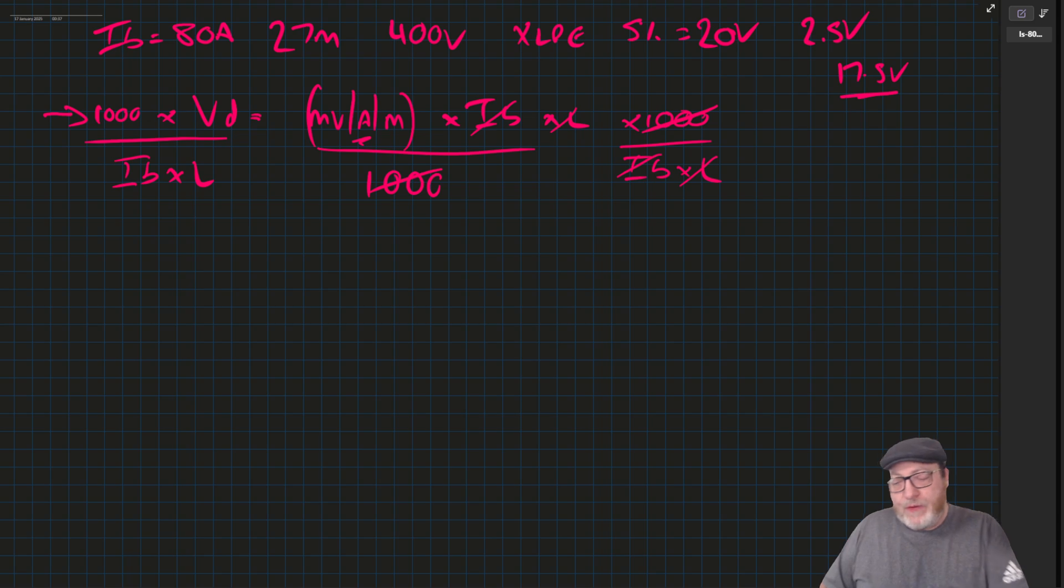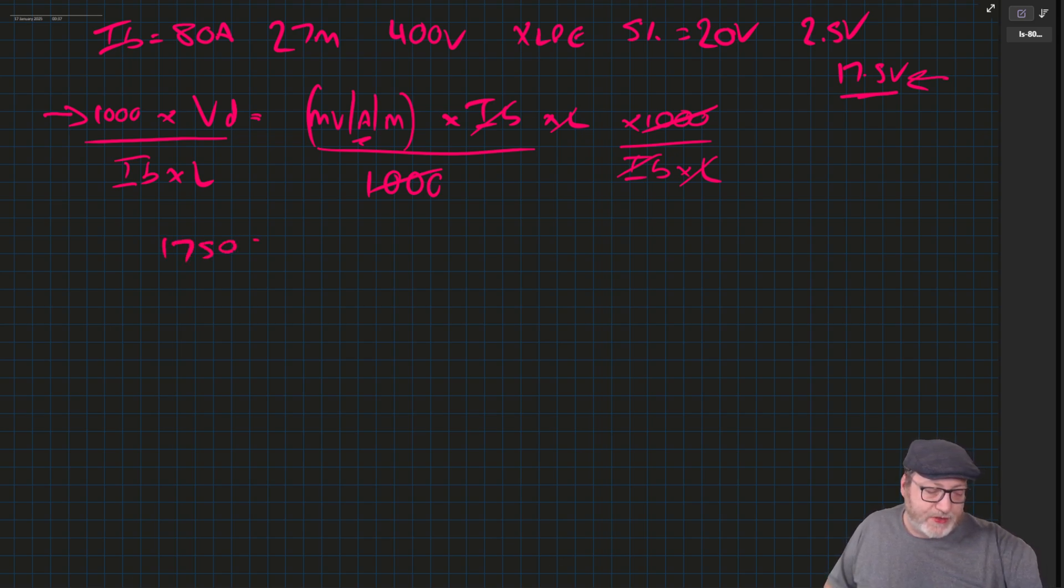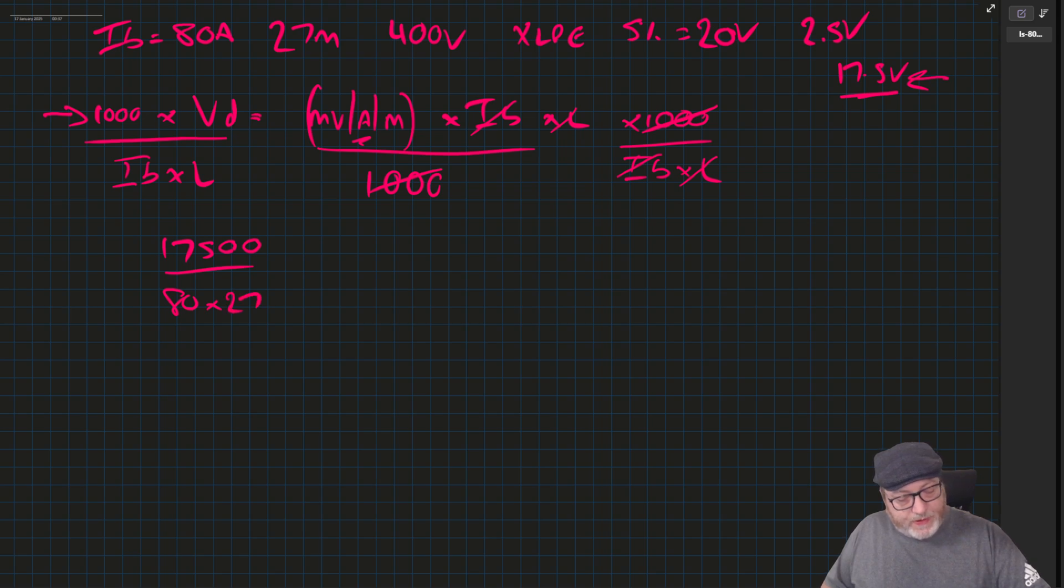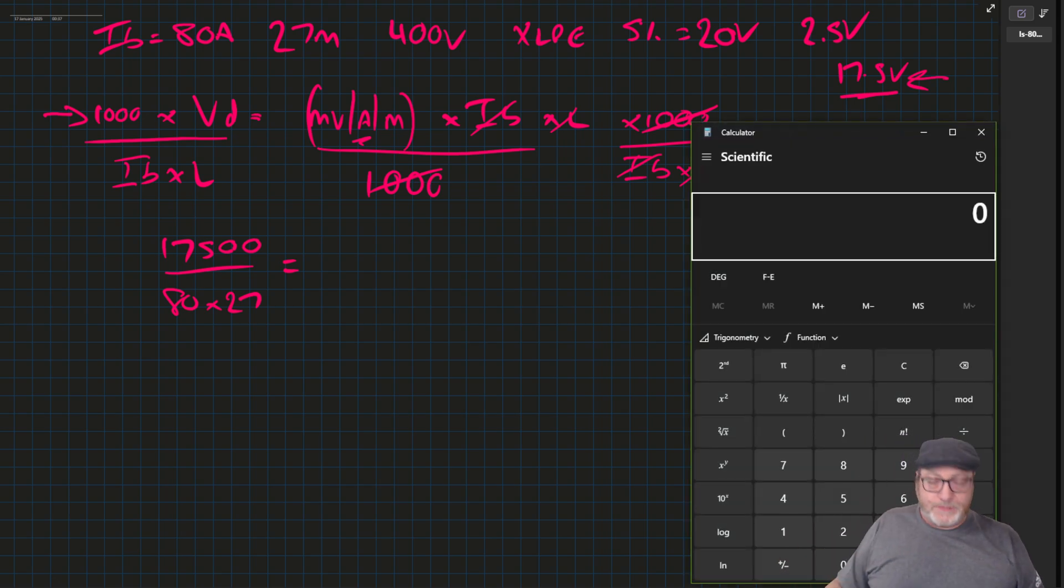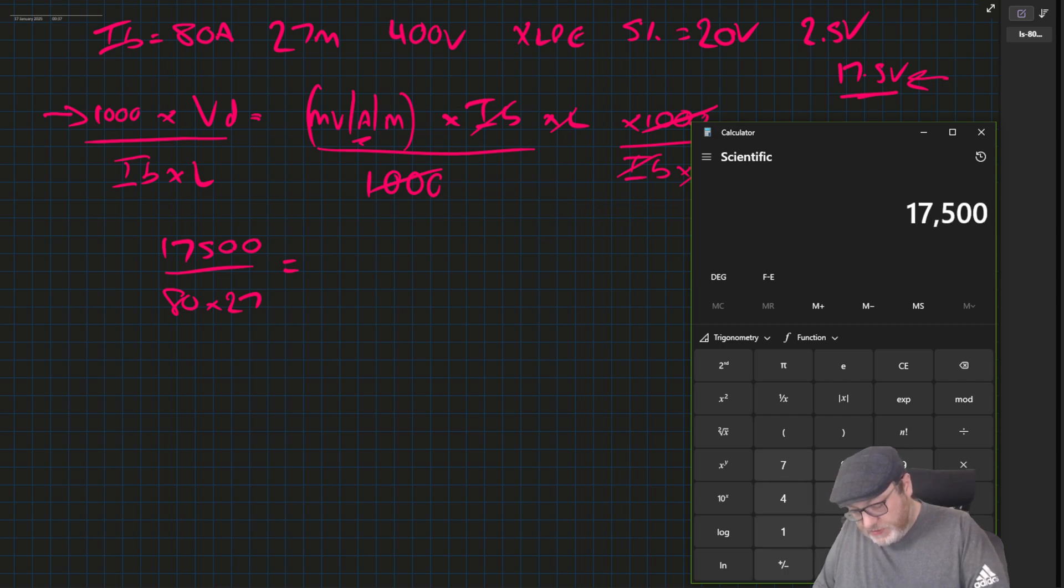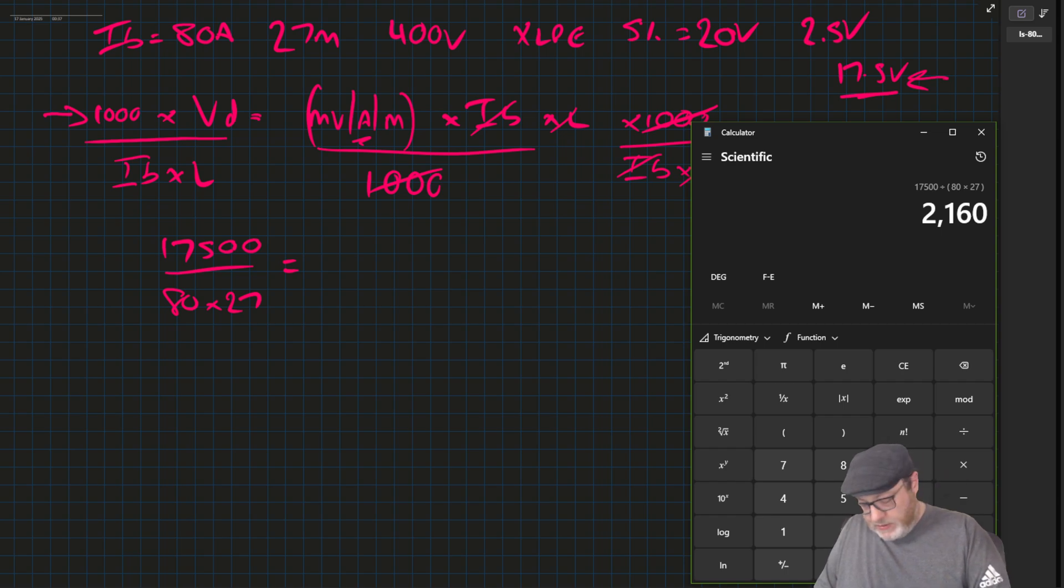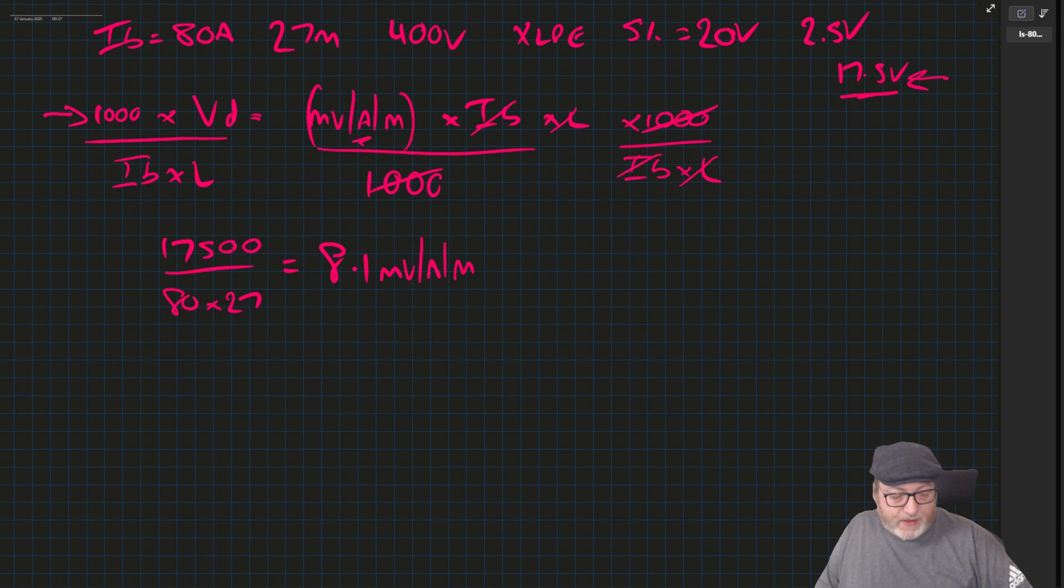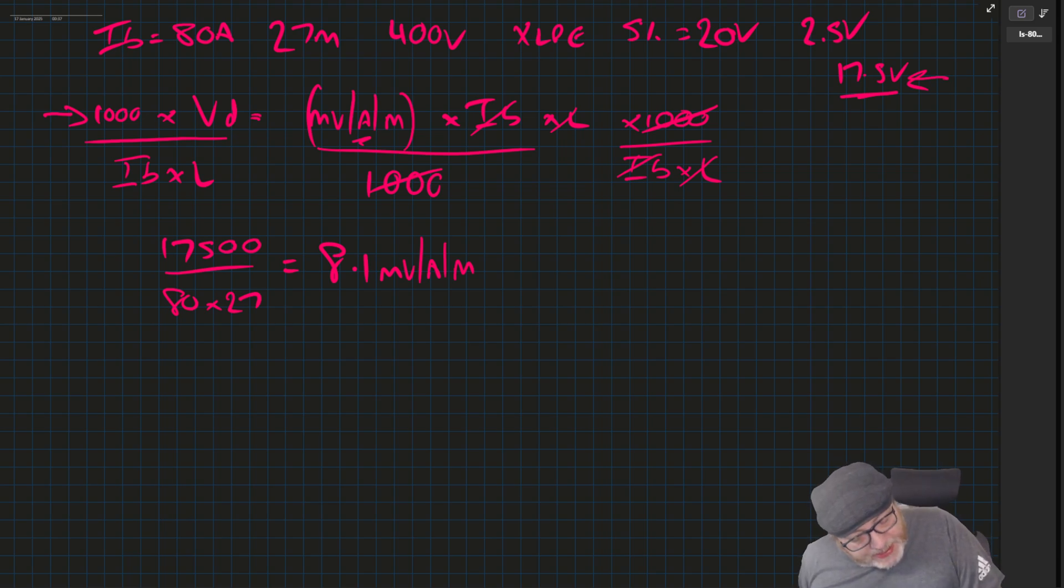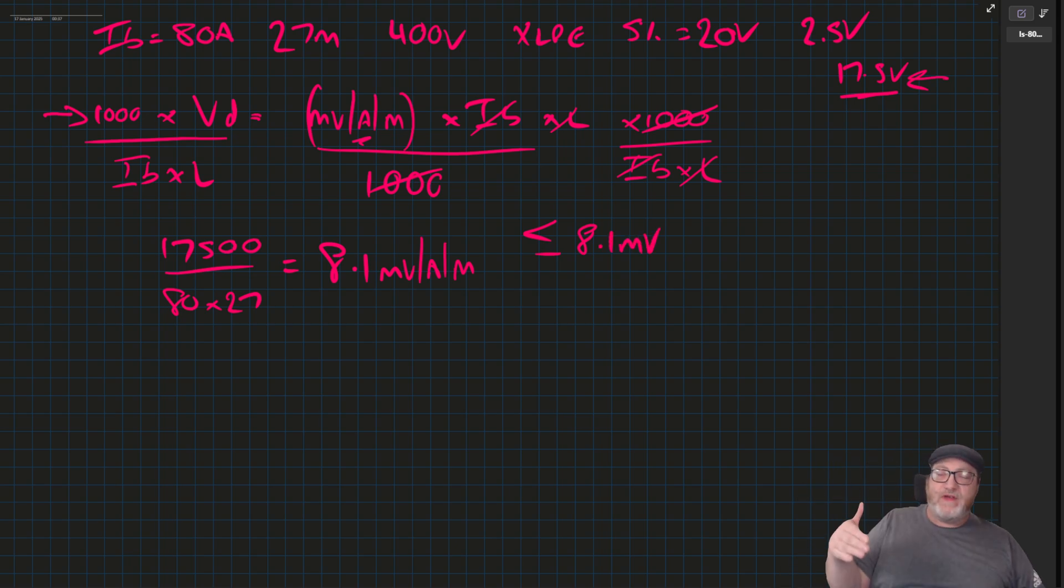If you know the volt drop we're allowed is 17.5 volts, because we've set that over here, that's going to mean the top line is 17,500 divided by 80 times 27. So we'll just work that out. 17,500 divided by 80 times 27 equals 8.1 millivolt per amp per meter. So that's obviously the maximum. We need to look for a number that is less than or equal to 8.1 millivolts when we look at our cable size.